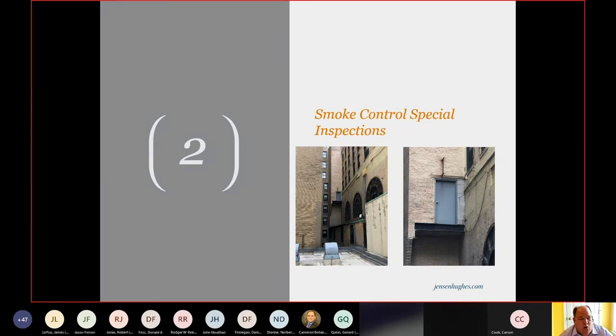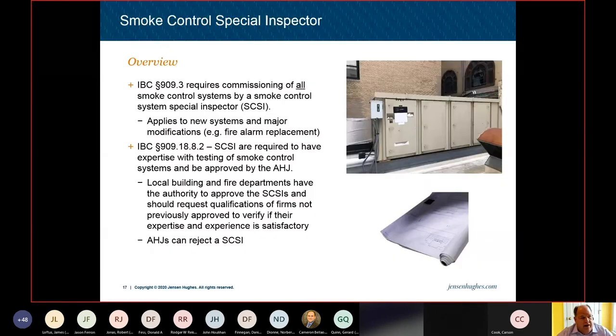You don't know what's on the other side of the door, and you get involved in the picture on the left is where that door leads to. It's a 30-foot drop. So, smoke control systems, you can get tied up and sucked in pretty readily because there's a lot of misunderstandings with smoke control systems. But the smoke control special inspector can be your friend.